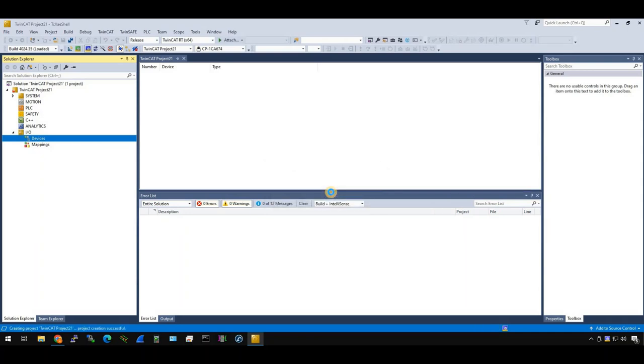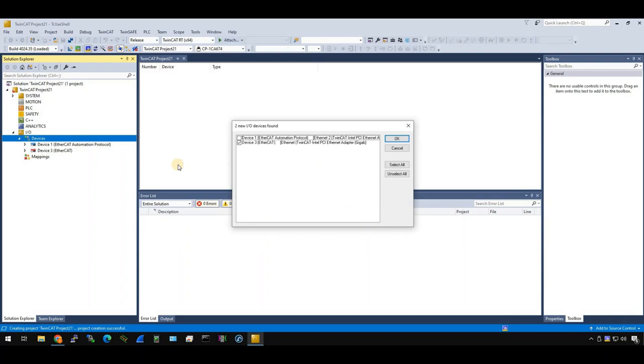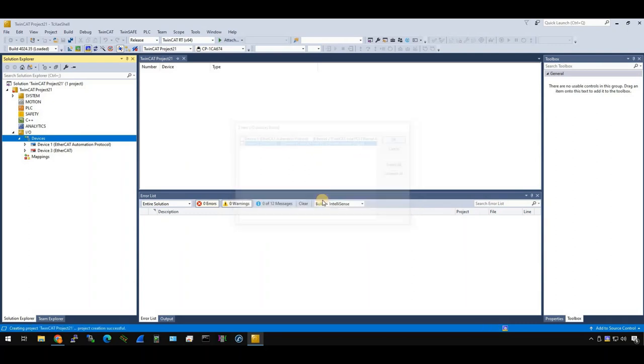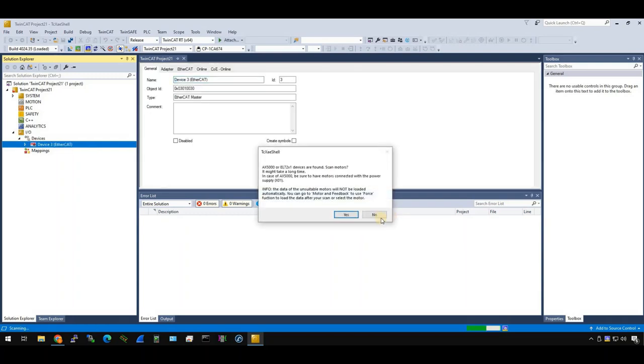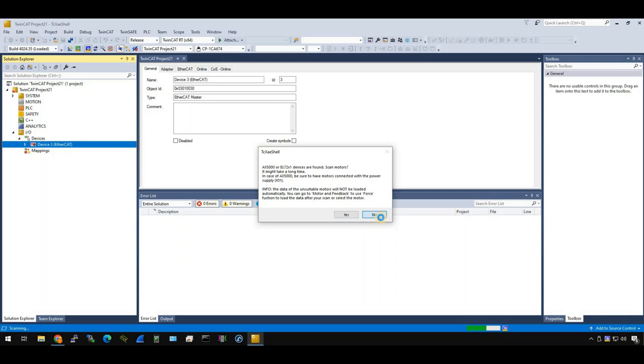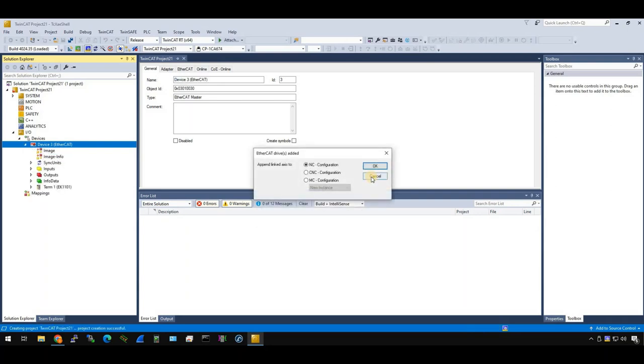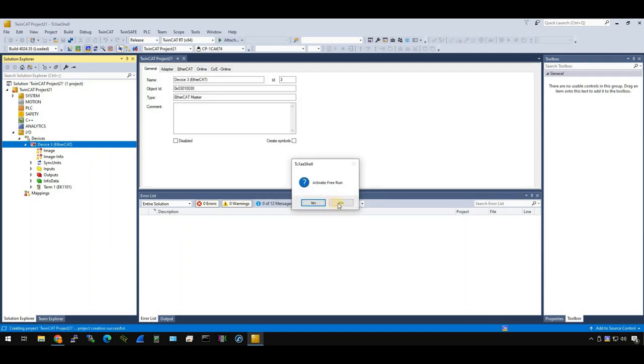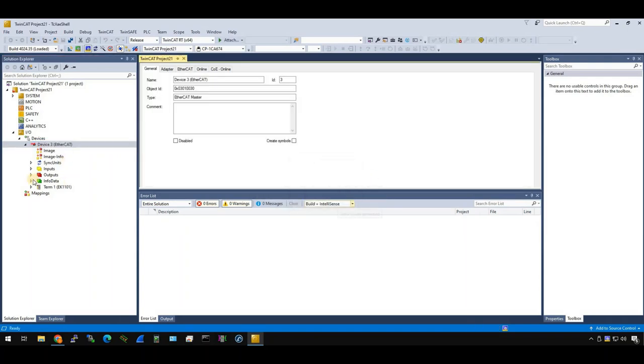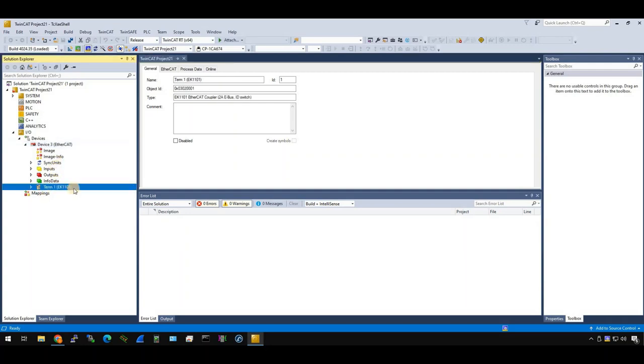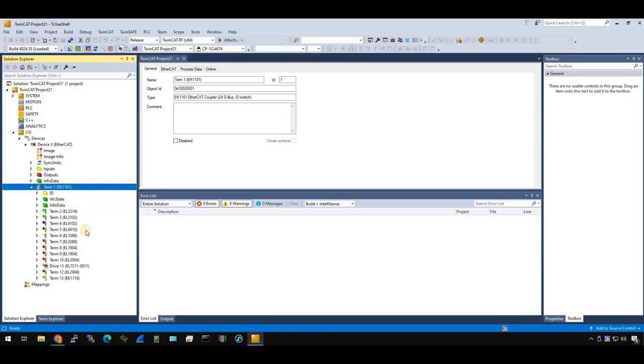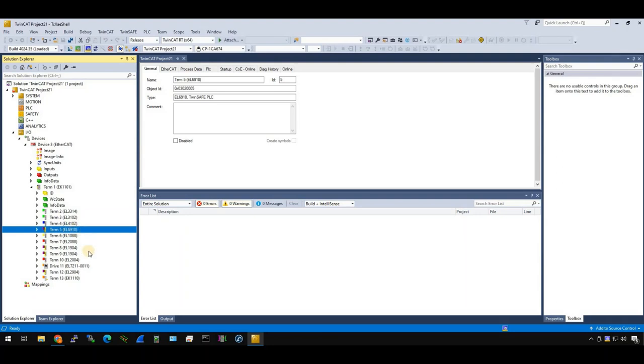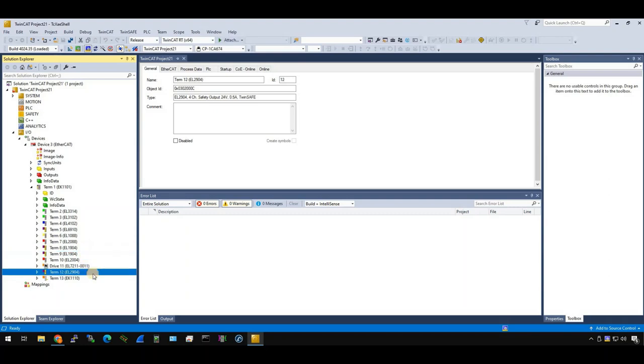So go to IO device, right click and scan the EtherCAT network. Which interface would you want to use? I want to use the EtherCAT interface. Okay. Scan for box. Yes. I don't need to scan my motor module, my motor terminal. I also don't need the access object. Okay. Now you see the terminal one has scanned EK1101. And inside EK1101, the terminal that I'm using this time is EL6910. And two safety input terminals, one EL1904, and also one safety output terminal EL2904.